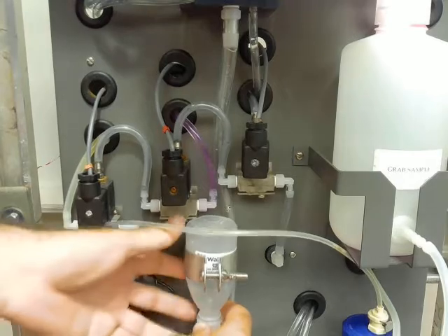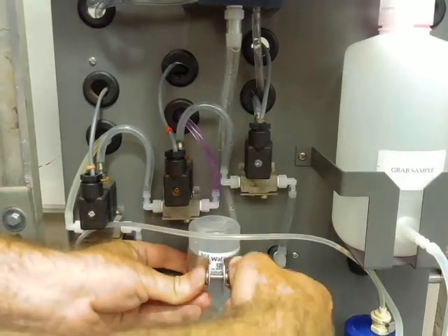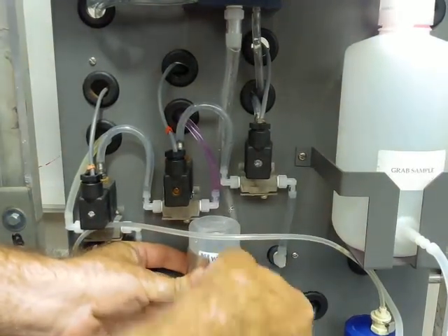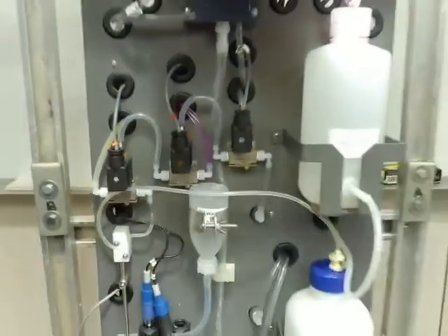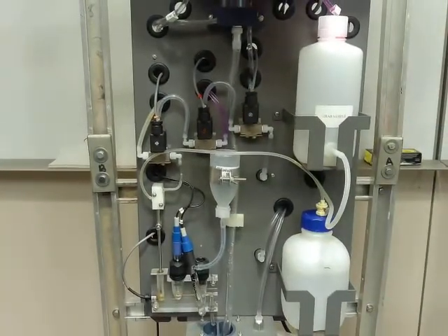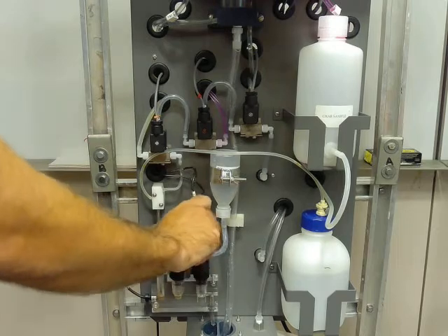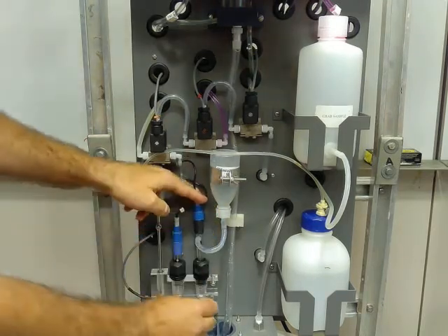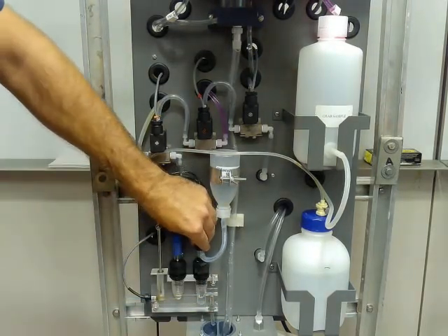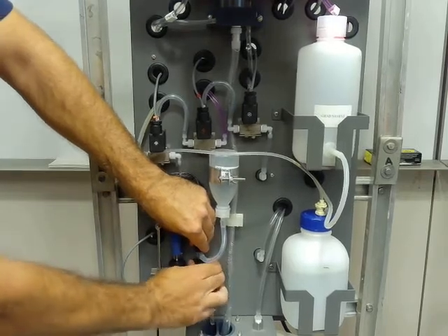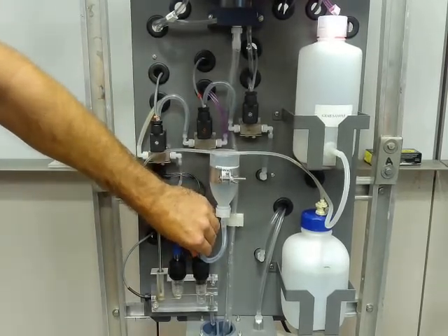If you are in a situation where it's been about 6 months and that bottle is still pretty full, you would want to go ahead and replace it anyway, and take a look at why that solution isn't draining through the electrode properly. Because as the sample flows past, the solution inside the reference electrode leaches through the ceramic tip of the probe.